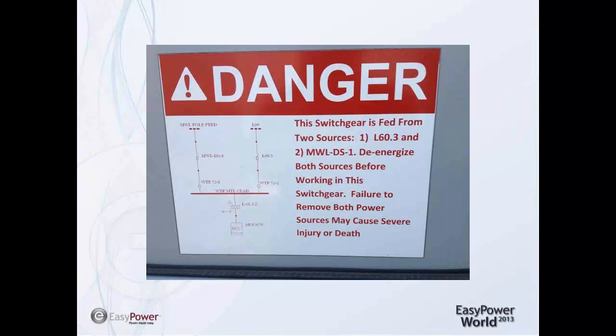I included this label because it's on a pretty unique piece of switchgear in our plant, since we're actually bringing power from our local utility in as a backup to our normal power feed. We don't do this anywhere else in the plant, so we use these red danger labels to warn people that there's something different, and that you need to know the difference before interacting with the equipment or doing a lockout, since there are more steps to this lockout.